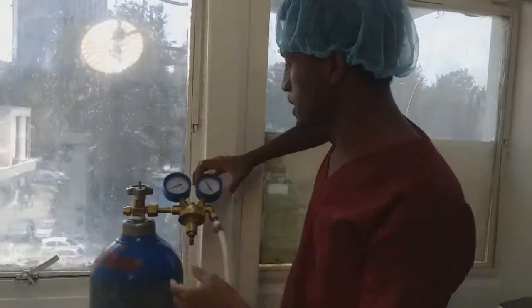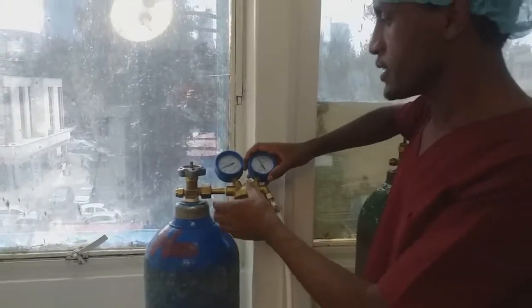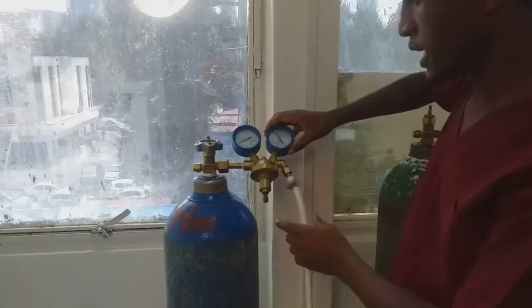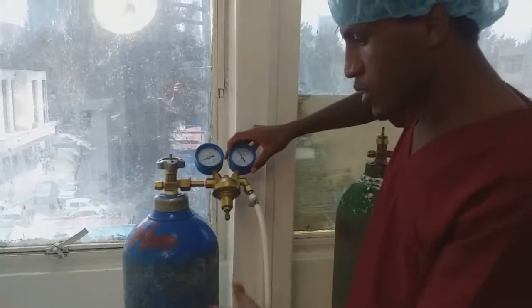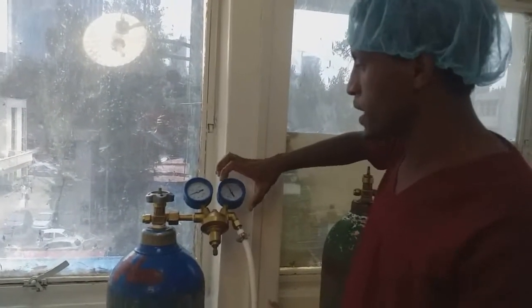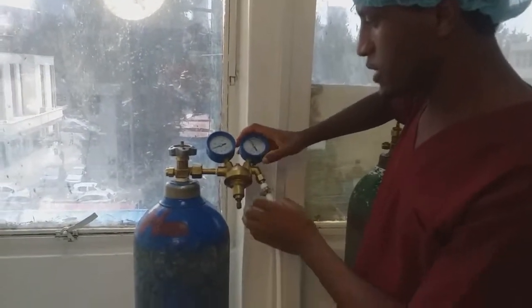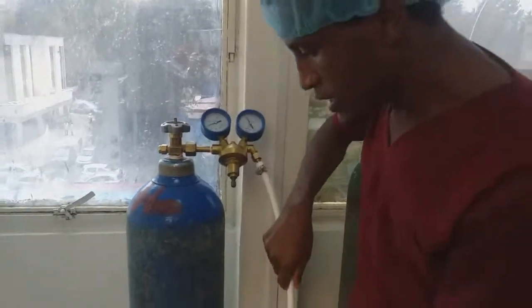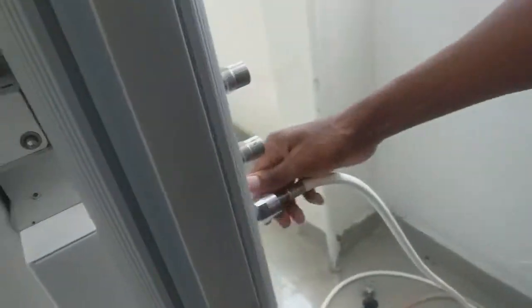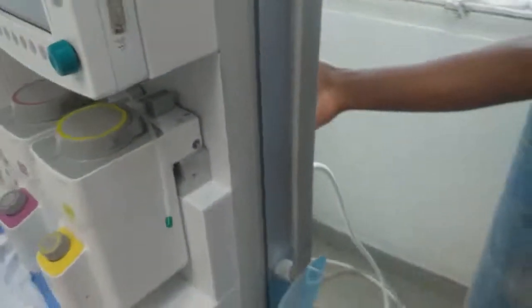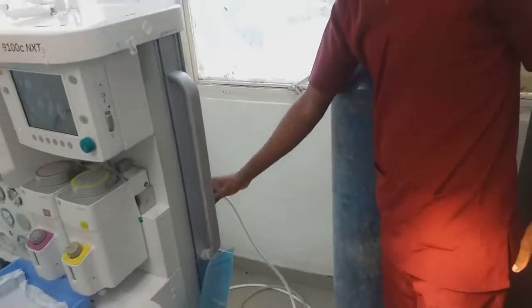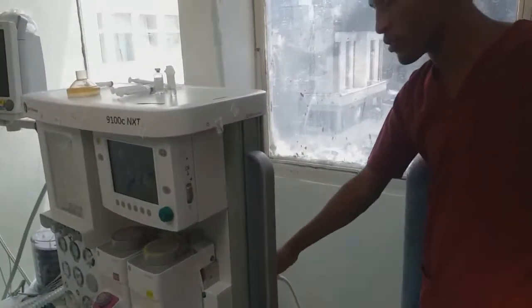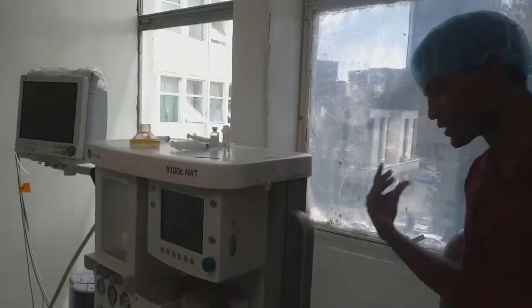And this is the pressure regulator. It regulates the high pressure coming from the high pressure system to convert it to the intermediate pressure system. This is around 5 bar. This oxygen pipeline should be properly plugged into the anesthesia machine. This is properly plugged in, in the appropriate hole, with the appropriate oxygen content and the appropriate cylinder.